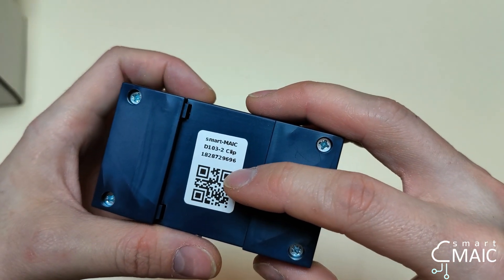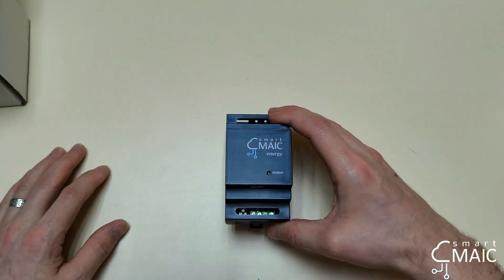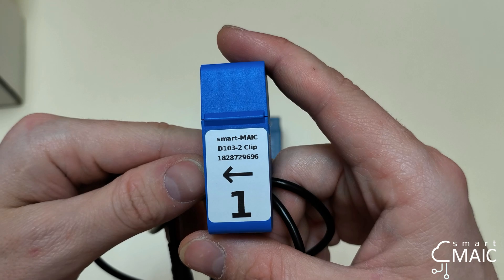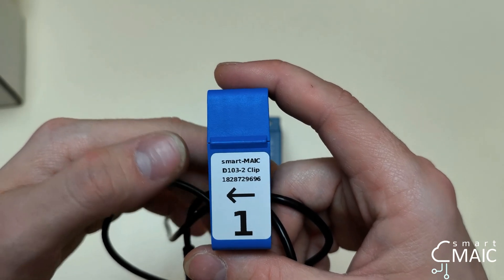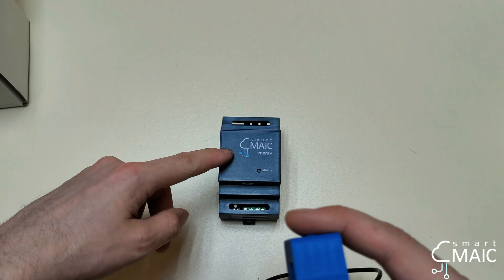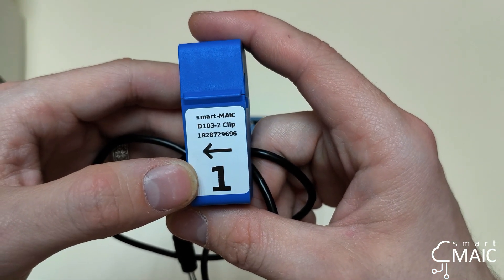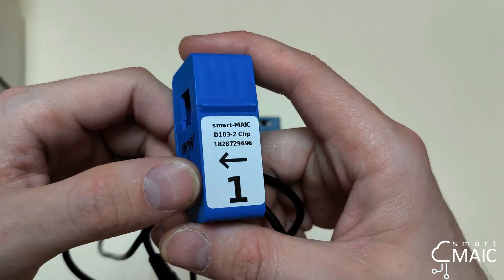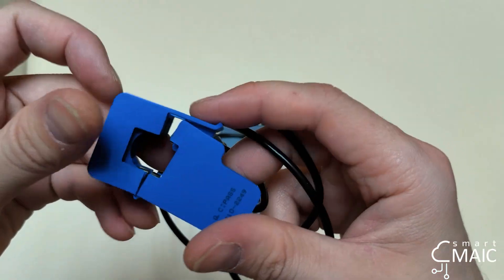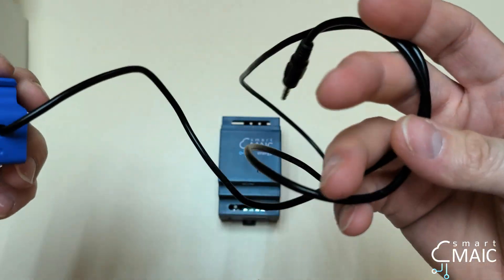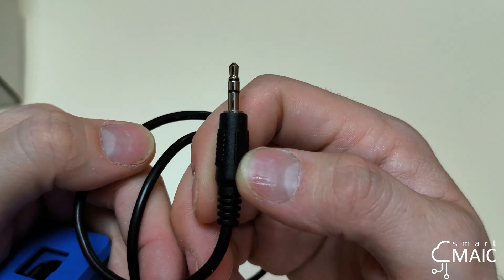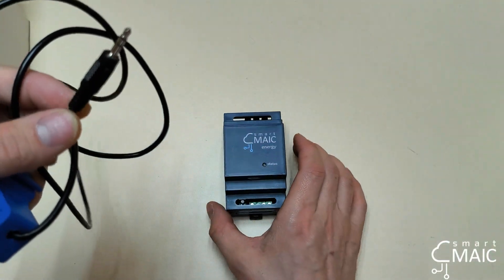Now let's look at the transformers. This is what our transformer looks like. It has the corresponding serial number marking which applies to this particular device, and also has phase numbering and a current direction mark. The transformer can be easily installed on wires. The length of the connection wire is one meter, and here is the connector for connecting to the energy monitor.